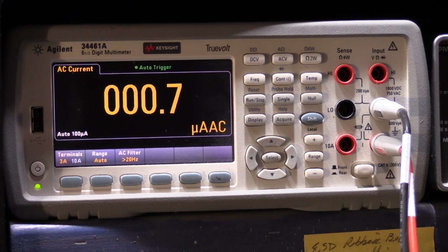So now we're going to change the setup back again to measure voltage. I'm going to measure the voltage coming out of the transformer while the chime is running. That's going to show us how much the output voltage of the transformer sags as the demand increases while the motor runs and the solenoids strike.